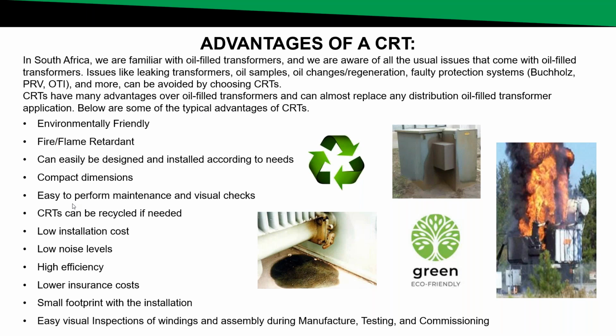It's very easy to perform maintenance and visual checks on cast resin transformers. The average maintenance time for a cast resin transformer is between half an hour and an hour. This involves cleaning the unit, torquing all the relevant electrical connections, and doing some basic testing on the unit. There is no need for taking oil samples and submitting and waiting for results. It is very easily maintained, and depending on the environmental and installation site conditions, it is recommended to maintain your cast resin transformer every 6 months to a year.